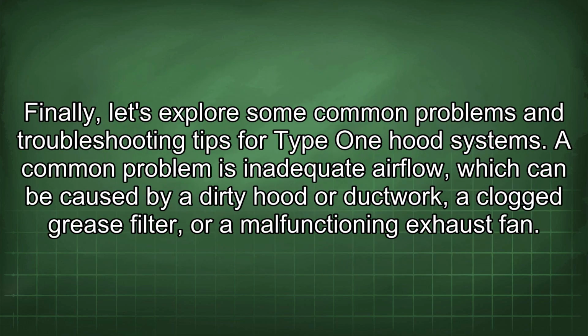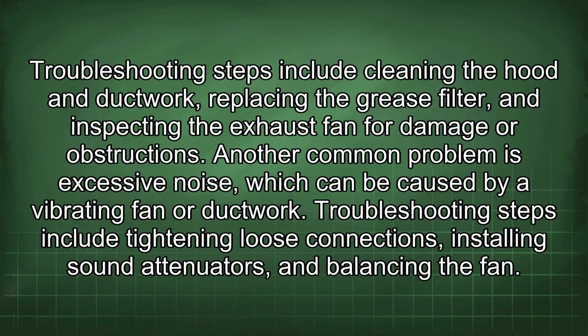Finally, let's explore some common problems and troubleshooting tips for Type 1 hood systems. A common problem is inadequate airflow, which can be caused by a dirty hood or ductwork, a clogged grease filter, or a malfunctioning exhaust fan. Troubleshooting steps include cleaning the hood and ductwork, replacing the grease filter, and inspecting the exhaust fan for damage or obstructions. Another common problem is excessive noise, which can be caused by a vibrating fan or ductwork. Troubleshooting steps include tightening loose connections, installing sound attenuators, and balancing the fan.